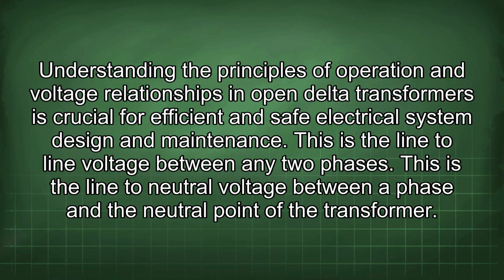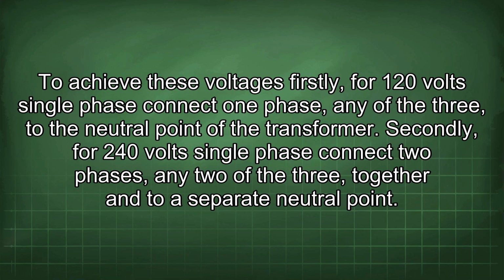Understanding the principles of operation and voltage relationships in open delta transformers is crucial for efficient and safe electrical system design and maintenance. This is the line-to-line voltage between any two phases. This is the line-to-neutral voltage between a phase and the neutral point of the transformer. To achieve these voltages, firstly, for 120 volts single phase, connect one phase, any of the three, to the neutral point of the transformer. Secondly, for 240 volts single phase, connect two phases, any two of the three, together and to a separate neutral point.